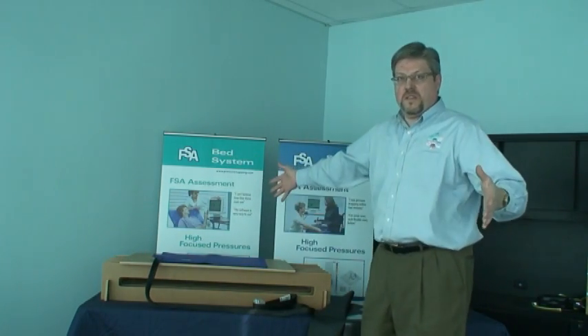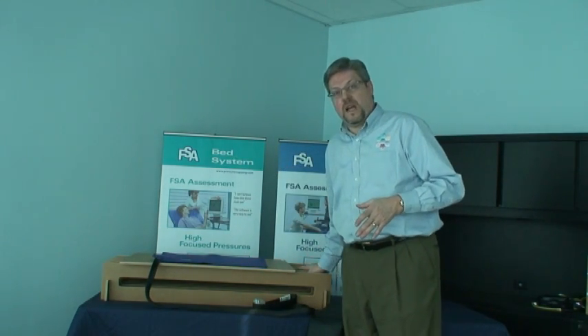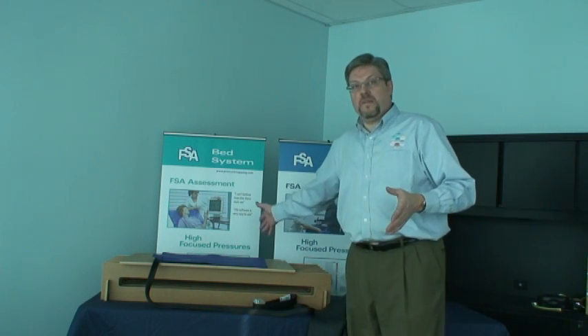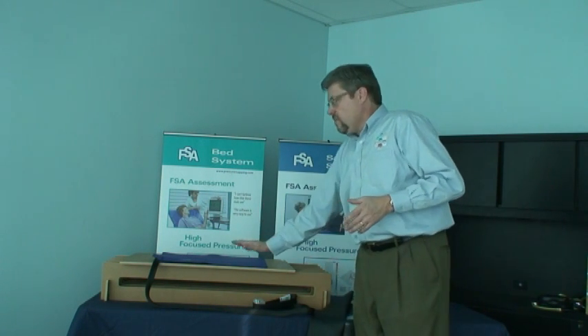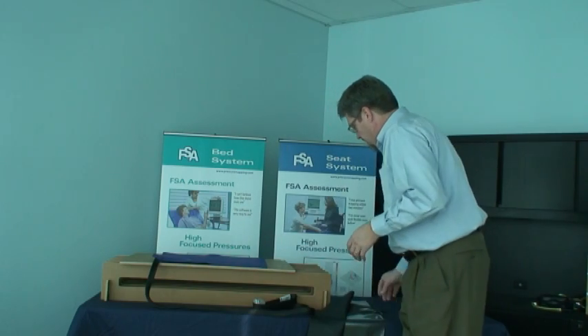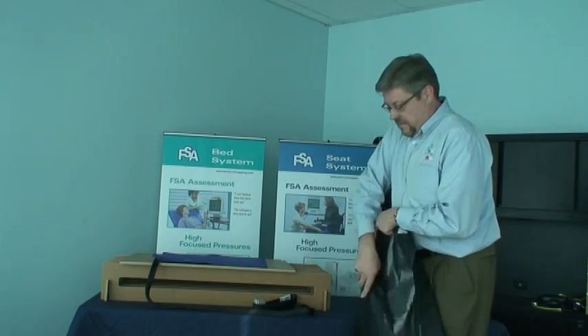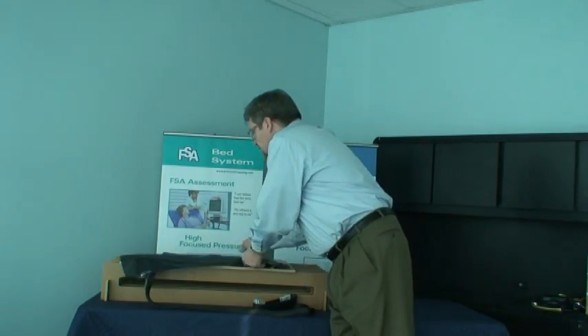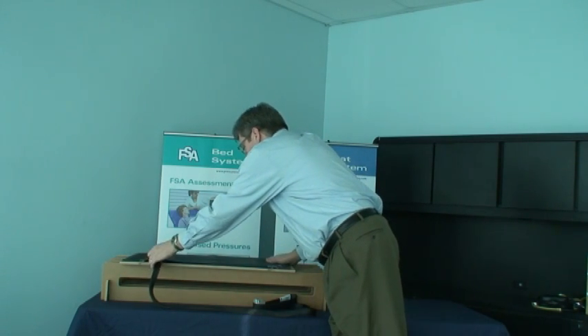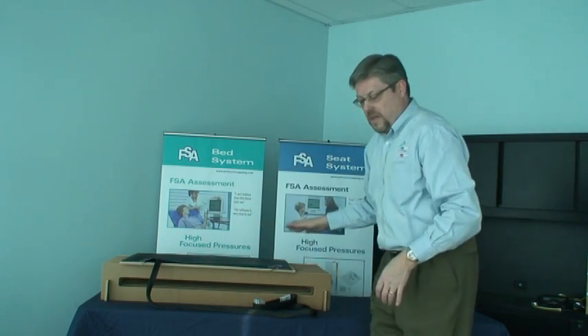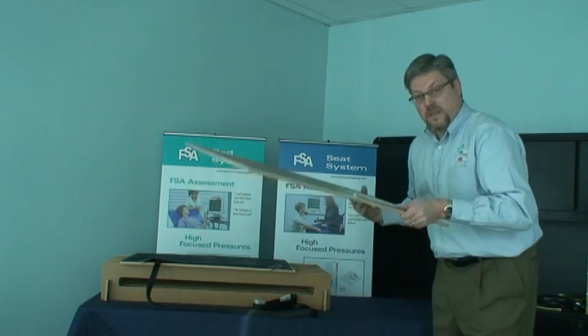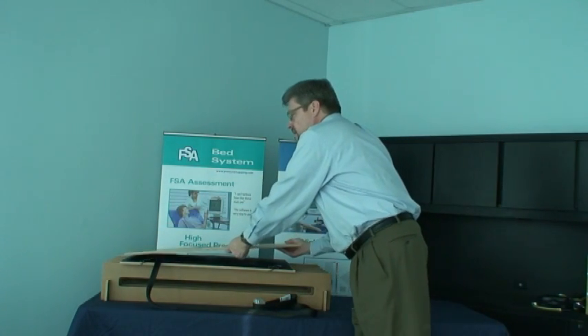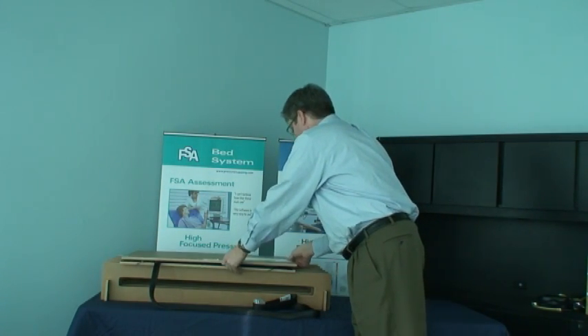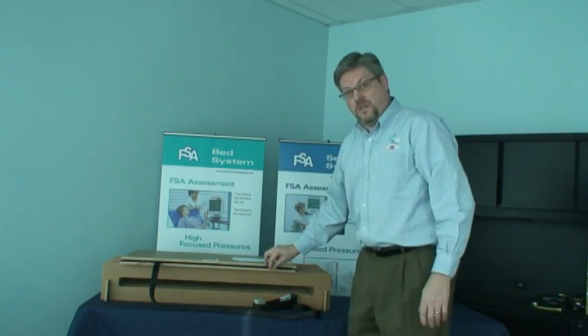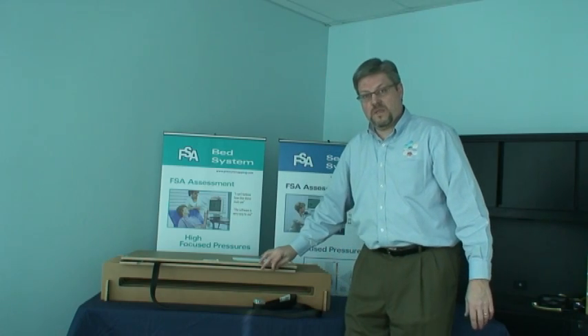Bed jigs, of course, will be 6 feet long, so you'll have more fingers and slats to work with. And of course, you'll have a platen that's 6 feet long. So place your sensing mat on top of that. Take your inflator. Place your inflator on top of the sensing mat. You want to center the mat underneath it. Then take the other platen, place it on top of the inflator. Of course, you've got your tubing on here now, right? One going to the pump, one going to the sphygmomanometer.